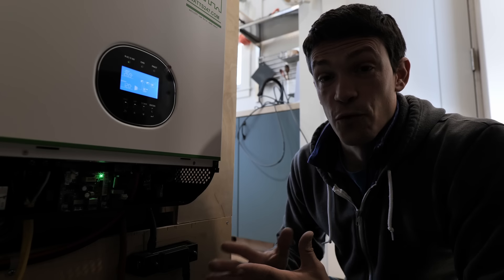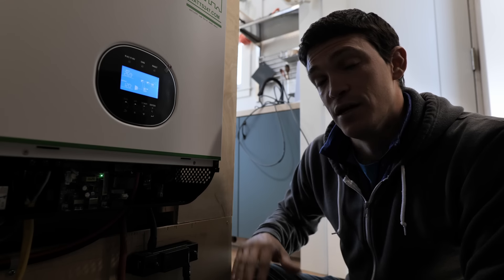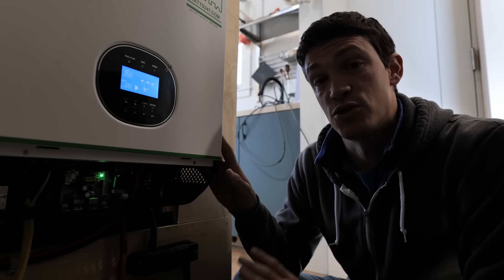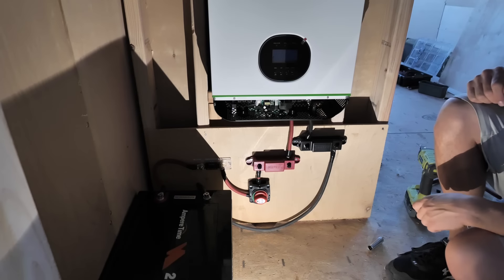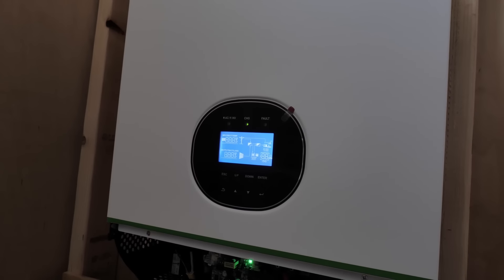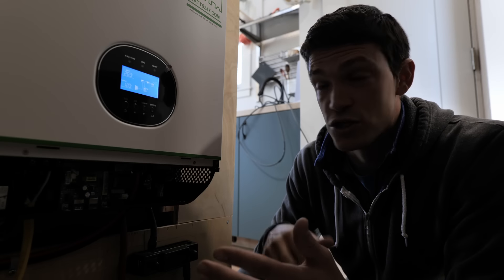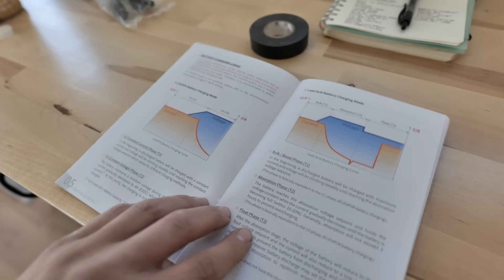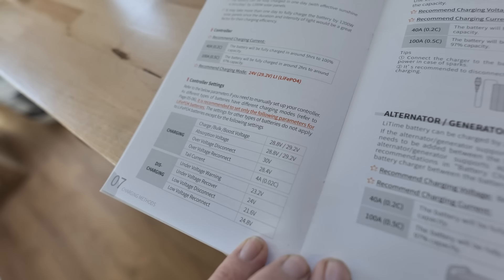Before moving on to the next step — doubling the solar input — I want to make sure my settings are correct in the Growatt. I did go through and set user settings for all the charging parameters during the initial install, but I just want to confirm nothing changed when everything reset. LiTime provides a very comprehensive product manual with all the charging parameters you need for these 24-volt batteries.